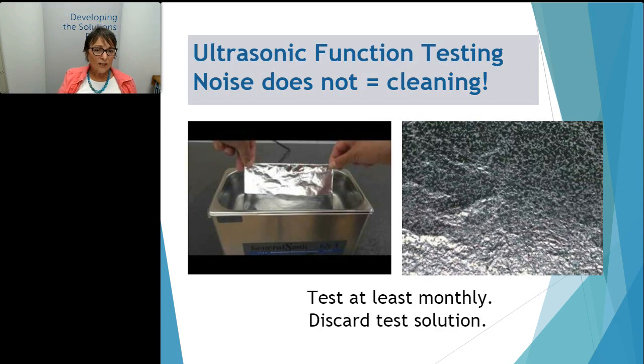Let's talk about function testing first. Ultrasonic function testing should be fairly straightforward. The main thing is noise does not equal cleaning—your ultrasonic might be making all kinds of racket, but that doesn't mean the transducers are actually producing the waves that create the bubbles. So you do have to do function testing.